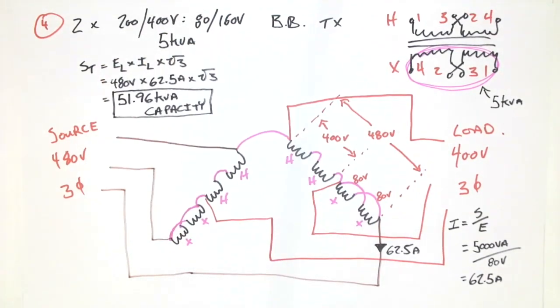That's insane. Absolutely insane. And so whenever we get the chance to install an auto transformer, we try to take it instead of an isolation type. There are some restrictions which you can find in section 26 under transformers that tell you exactly when you can and cannot use an auto transformer. But man, if you have the option of choosing either an auto transformer or an isolation type transformer, you are going to get some monumental cost savings by choosing the auto transformer arrangement.